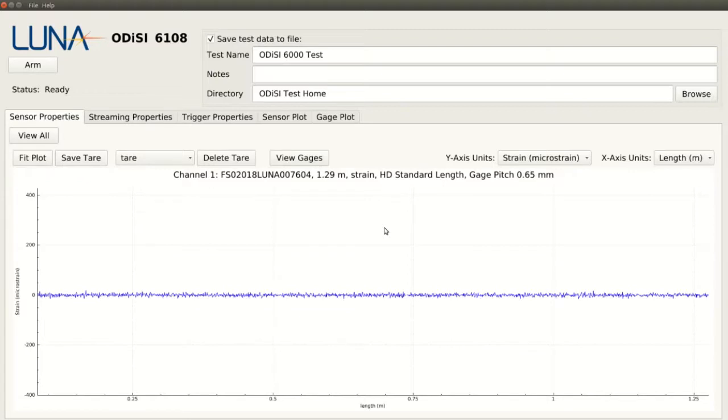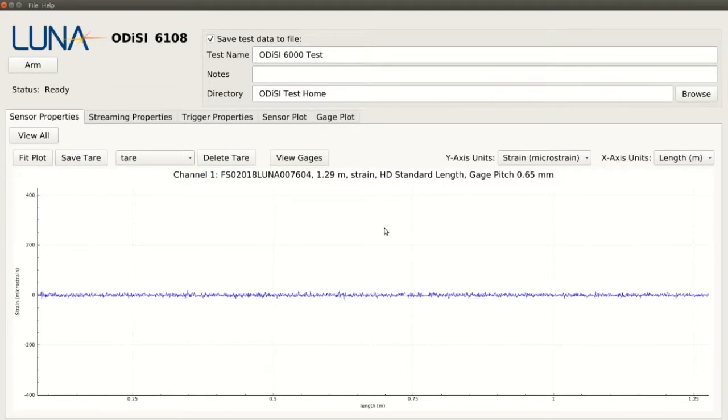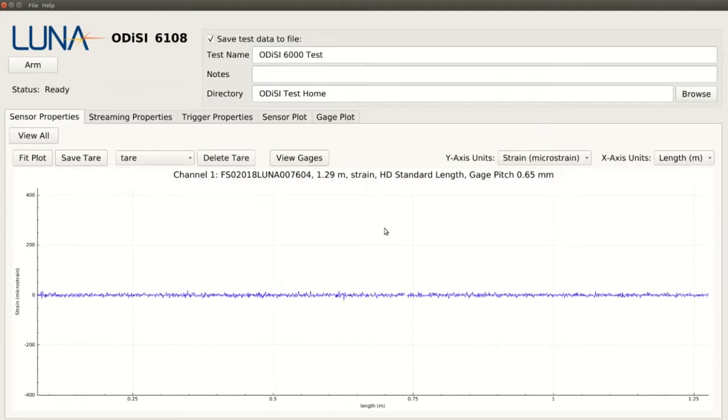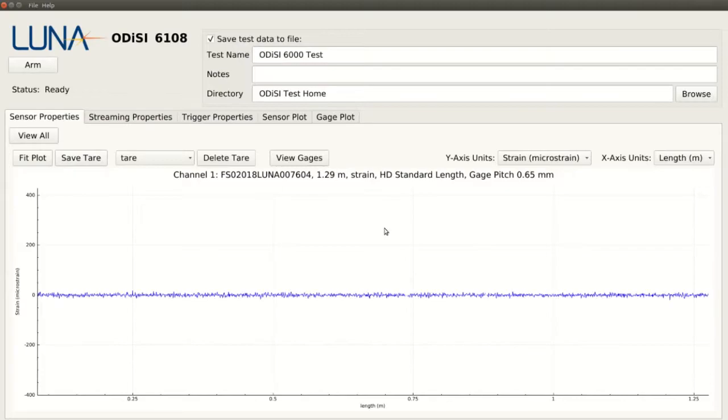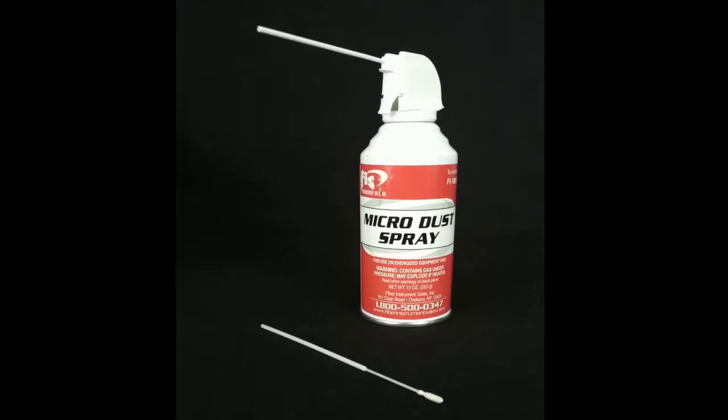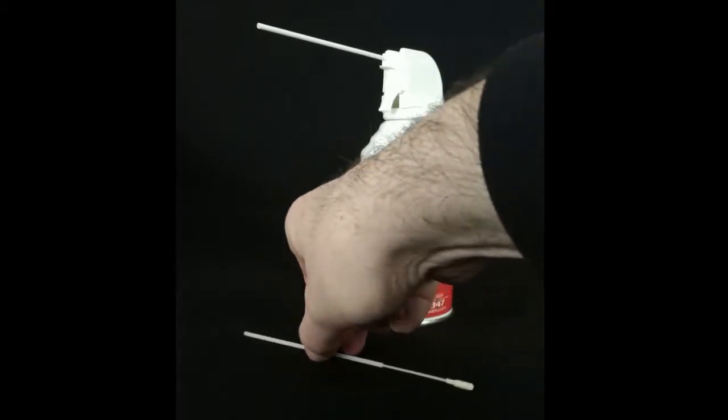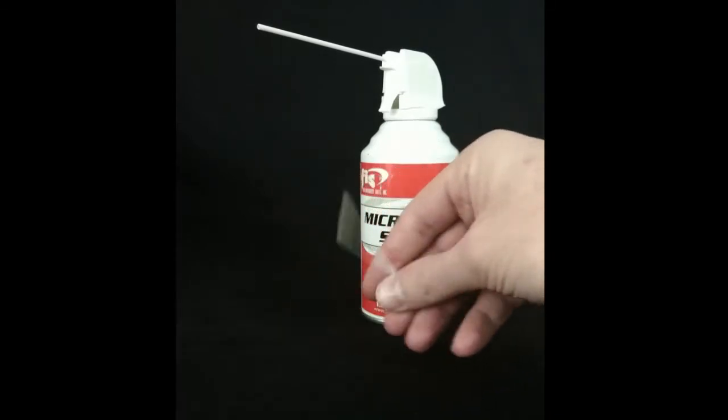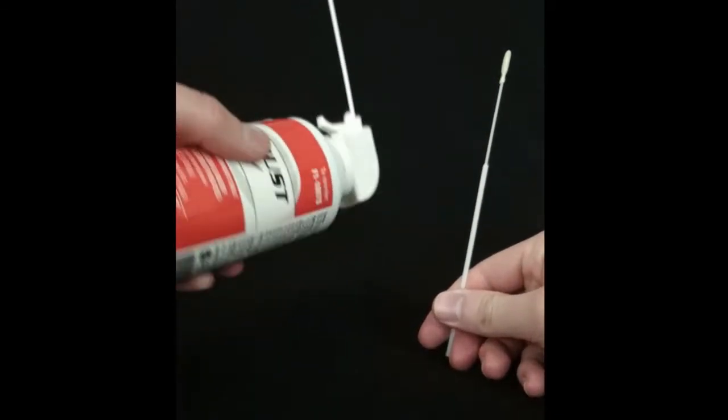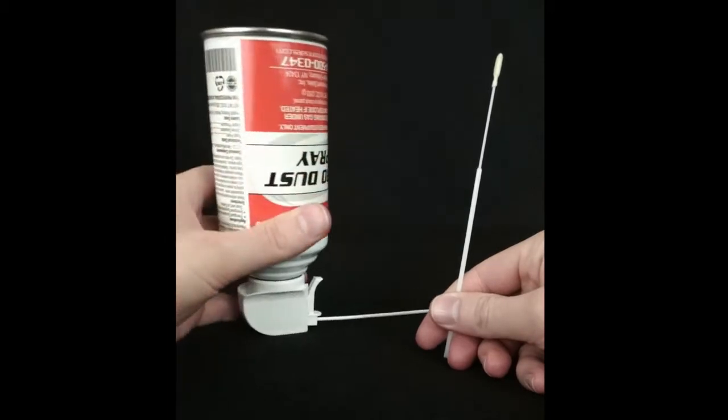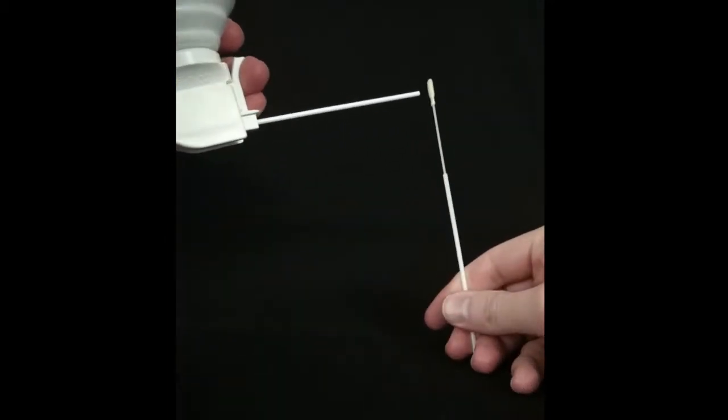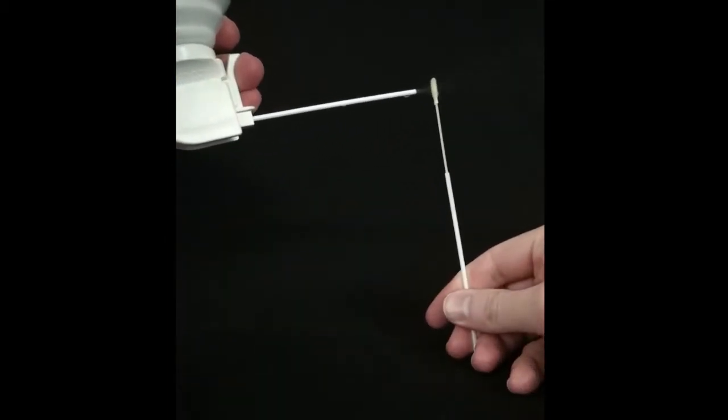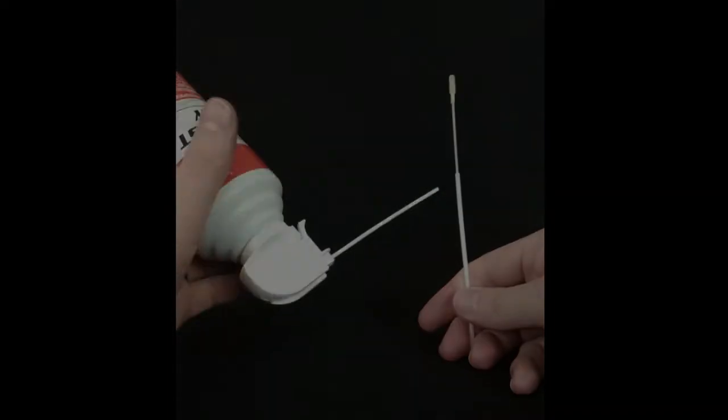At this point, it is usually a good idea to do some form of touch to locate. This process is what orients the sensor to the physical component by defining interesting points or segments which will be useful for data interpretation or analysis. This is most easily done with a Q-tip and a can of compressed air. When the can is held upside down, the spray releases in a supercooled state and flash freezes the end of our Q-tip. When we use it to touch a spot on our sensor, it appears as a negative strain spike that can help us map out where the sensor is spatially on the component.